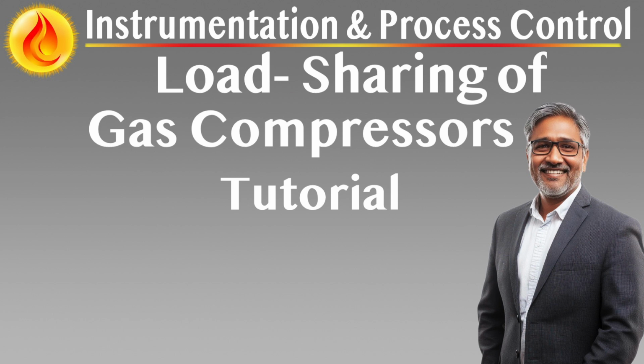These systems operate by intelligently coordinating the operation of each compressor so that all units remain equidistant from their surge control limits, thereby distributing load safely and responsively across the entire network. The goal is to avoid the inefficiencies and vulnerabilities seen in traditional approaches where one compressor might recycle unnecessarily while others remain underutilized. A properly configured load-sharing framework maintains process stability and protects all machines, even during disturbances, turndowns, or rapid demand swings.